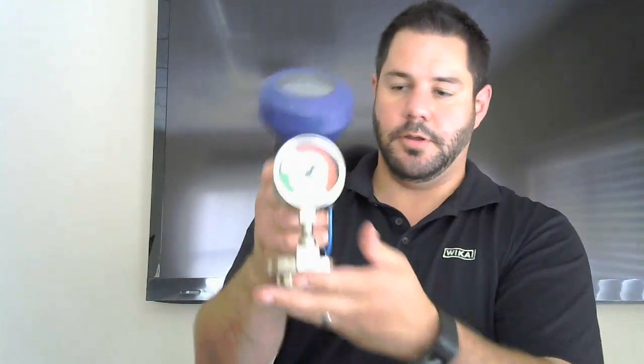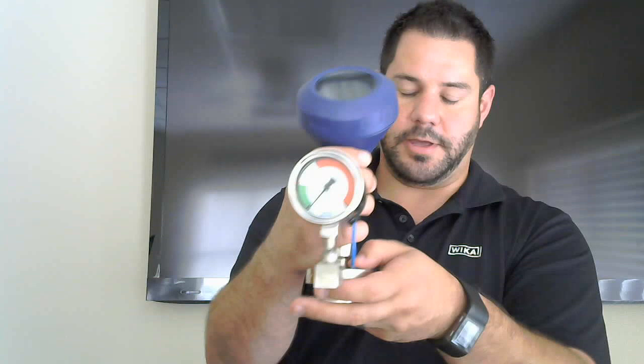So let's say, for example, if you're running your process and this thing would go off and indicate that you've had a failure, you could finish your process, come out, open this thing up, and look. And if you saw that down here this diaphragm is the only one damaged, but the other one's still intact, then you know that your process has been able to be kept clean, so that you don't have to quarantine or anything of that nature.